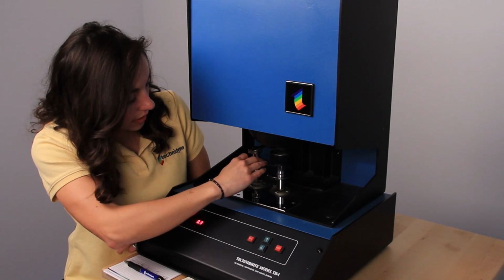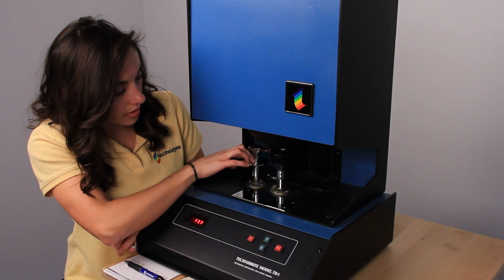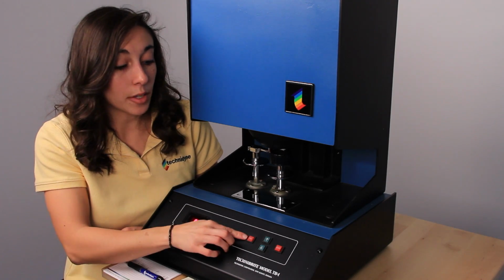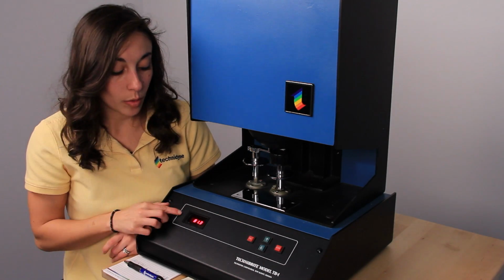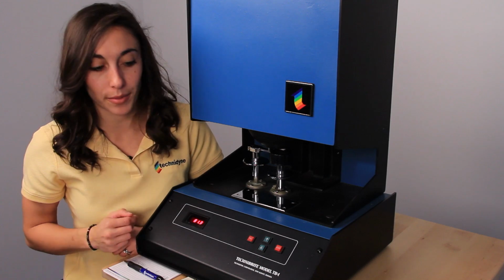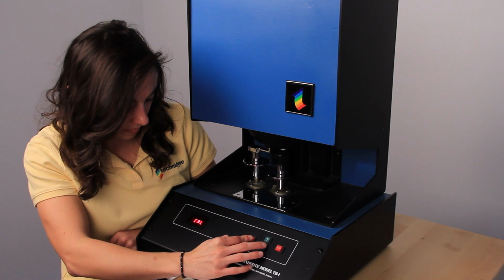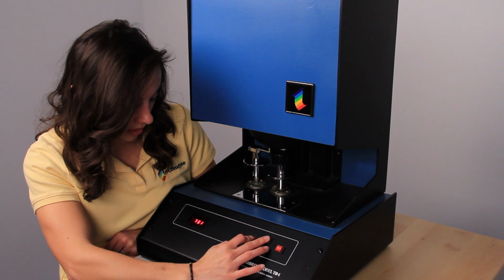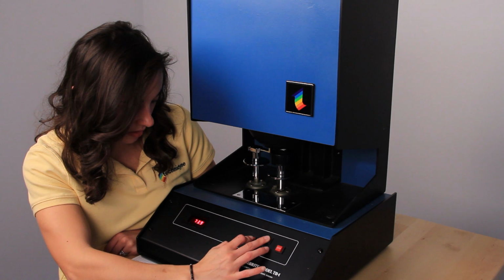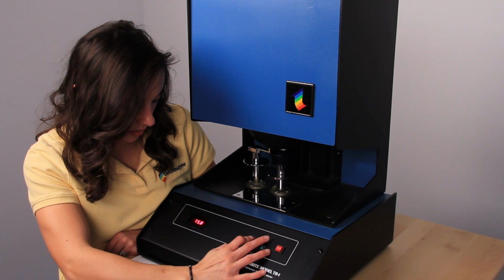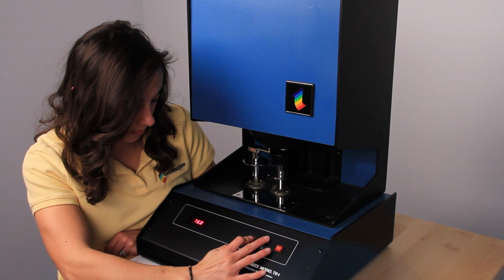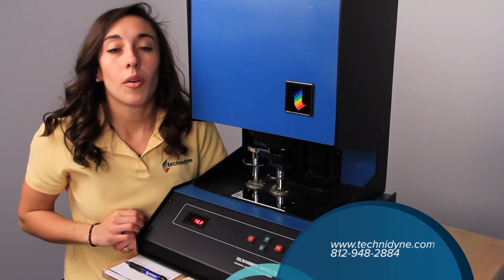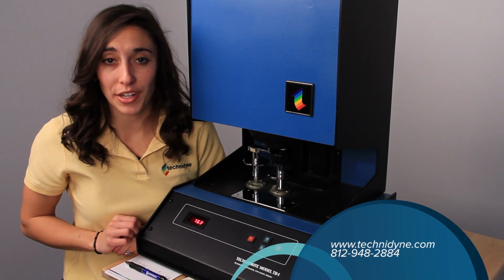We'll load the swing-in standard. And once again, using the Calibrate and the up and down arrow keys, we'll match the display number to the number that we wrote down earlier. Once you've got your numbers equal, our calibration is complete.